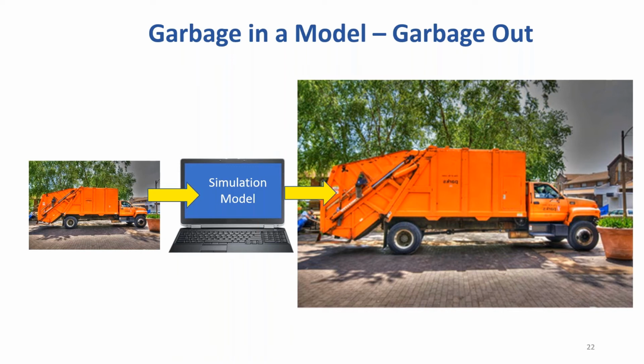A few years back, my first virtual commissioning client had this very problem in the past, which was not discovered until the plant was built and didn't meet the throughput goals that the model indicated could be met. And you guessed it, the problem was that the model did not model the same control logic as the PLCs. So they wanted to ensure that they didn't get burned again.